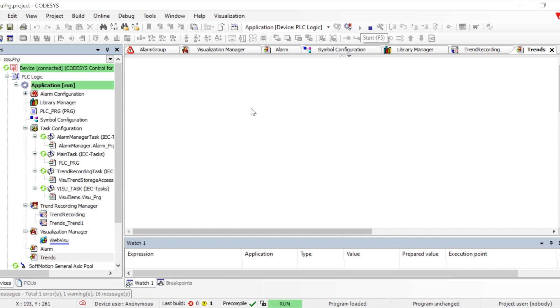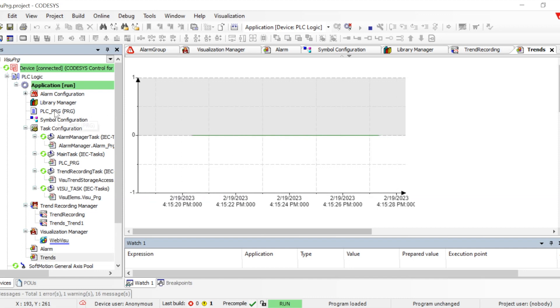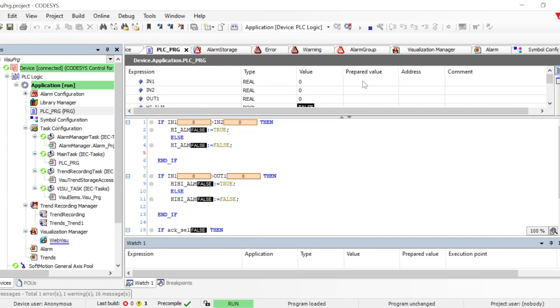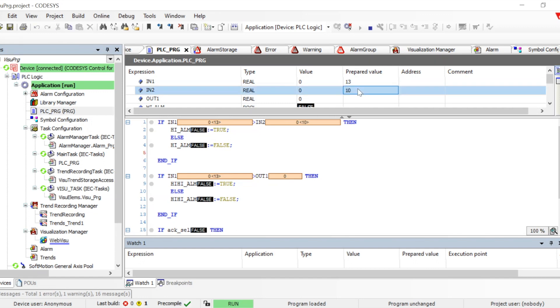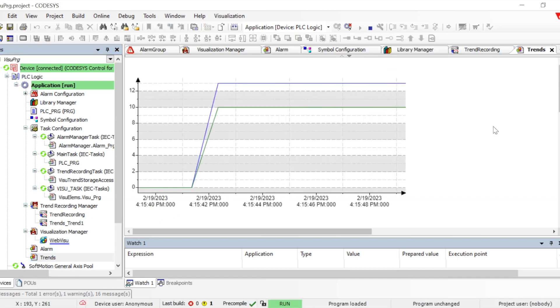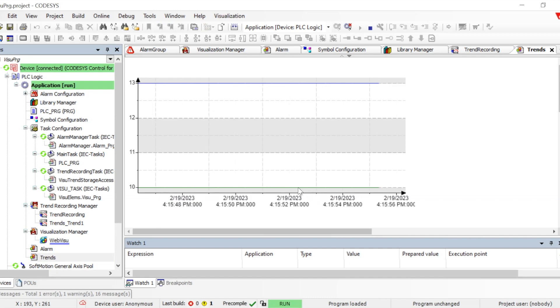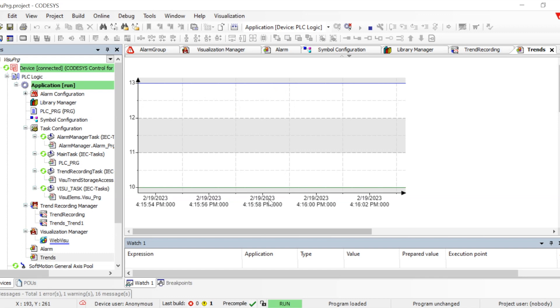Once downloaded, let's change to Run Mode. We can see that the data is getting plotted. Let's change the data of the variable — right now it is zero, so let's make it 13 and the other to 10. Now let's go to the trend and see how it changed. You can see the dip — it is plotting in a different way. All values from zero changed: one variable to 13 and the other to 10, shown in two different colors with time and date — trends are getting plotted.